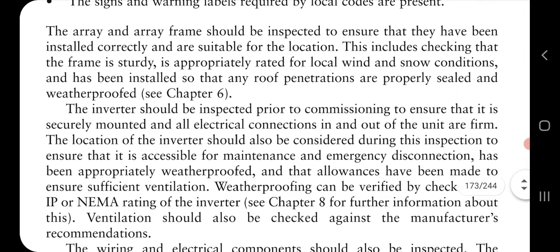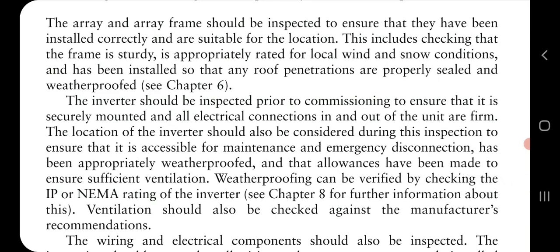After that, the array or array frame on which the PV cell is mounted has to be inspected and checked correctly, and it should be sturdy. We have to check that there is not any disturbance caused by wind or snow, and it should be weatherproof. The inverter plays a very important role. So before starting commissioning, inspection has to be done. The wiring connection has to be checked. The location of the inverter should be considered, because it should be accessible for maintenance and emergency disconnection, and it should be waterproof.